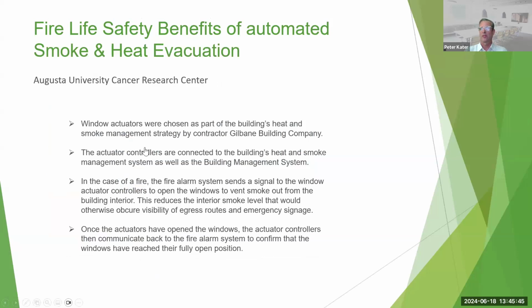For this project, the actuators were selected during the design phase as part of the building's heat and smoke management strategy by the contractor. The window controllers are connected to the building's fire alarm system, and also to the building management system. So this enables natural ventilation strategies to be used, as well as, in the event of a fire, the smoke and heat evacuation functionality. When a fire occurs and is detected by the fire alarm system, that system sends a signal to the window actuator controllers to open the windows, particularly the high windows or skylights, to vent smoke and heat out of the building interior.